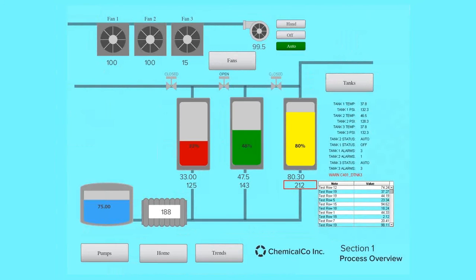Here's our first revision of that layout. You can see that we've removed the animation and a number of the elements that weren't critical for the operator view. We've simplified the graphics and gotten rid of distracting elements like the shading and the cutaway effects. The result is something that is a lot simpler, easier to read, and a lot more iconic.